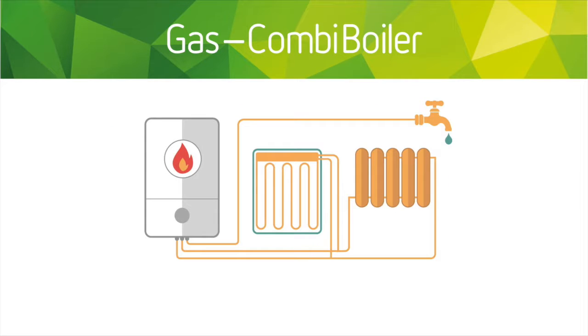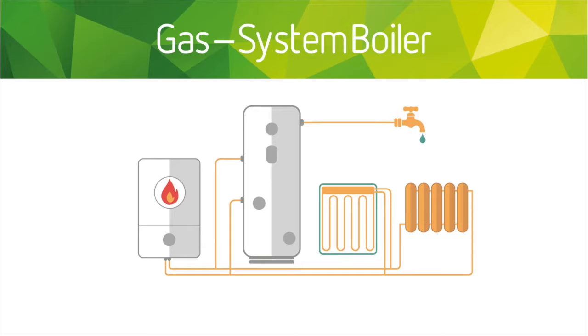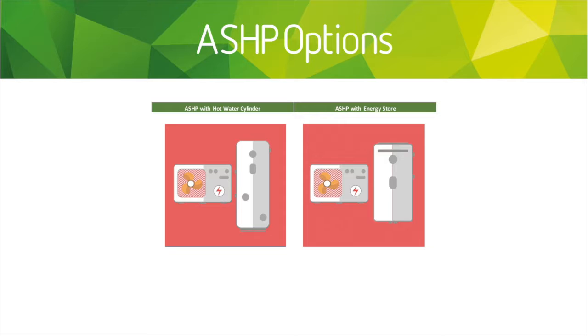So, gas combi boiler schematic: the combi boiler generates the hot water and also then generates heat for the heating systems. Typical sizes are not too dissimilar to what you've seen before. Combi boilers are pretty much the same size. Gas system boilers provide heat to either the hot water cylinder, the underfloor heating or a radiator system. The only difference compared to a combi boiler is that you need to allow space for a hot water cylinder, which is typically around about 700 by 700, up to about 300 litres, because the cylinder virtually extrudes upwards rather than outwards.